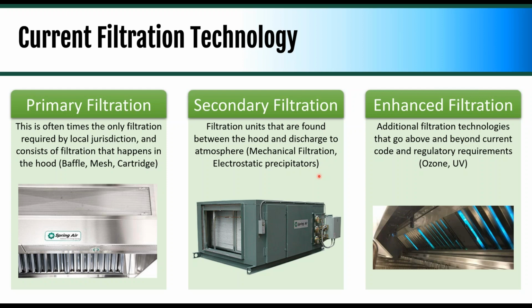So that's where I prefer the media-based filters, the mechanical filtration, just in terms of they're always removing the grease from the air. And the last thing, and this is where we're starting to see others get into, is enhanced filtration. These are filtration that go above and beyond current code and regulatory requirements. The two biggest ones you've seen or heard about are ozone and UV. Both have good and bad parts to them. We like to combine them both, which you'll see as we talk about, well, you heard it in the video too.